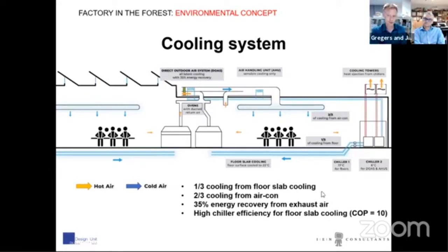The good thing about this floor slab system is it uses a very high efficiency chiller, in this case a magnetic bearing chiller. Because the chilled water temperature is at 17 degrees instead of the normal 6 or 7 degrees, the COP, or coefficient of performance, was very high, around 10.